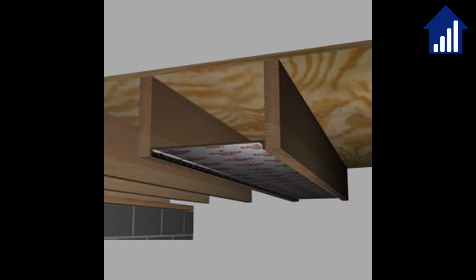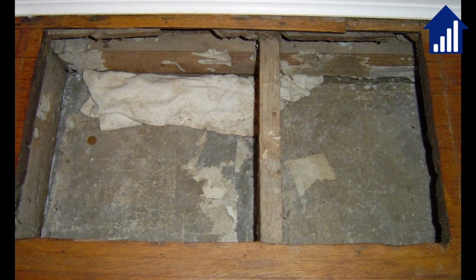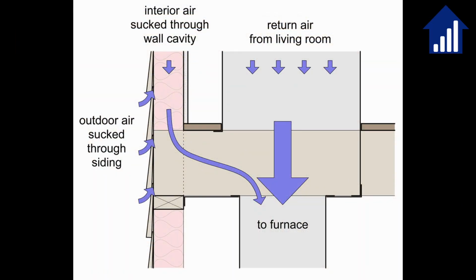Well, all of the return ductwork is actually panned, meaning this house uses the walls as the return ductwork. I'll say that again. The house uses the interior walls and some exterior walls as the returns. So these are the ducts that are bringing air back to the furnace. So what's happening? Well, we have return ductwork. Wherever we have return ductwork, when the system is running, the return ductwork gets depressurized. And we're literally using wall cavities to suck air back down to the furnace. Well, the walls that we're using, or those cavities in the walls, they're actually connected to the attic.